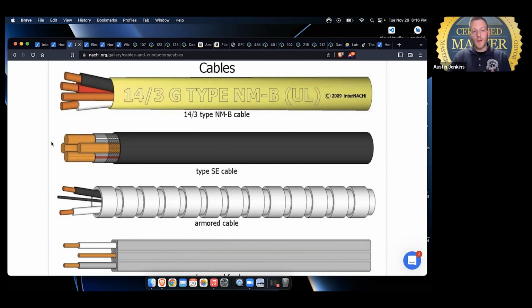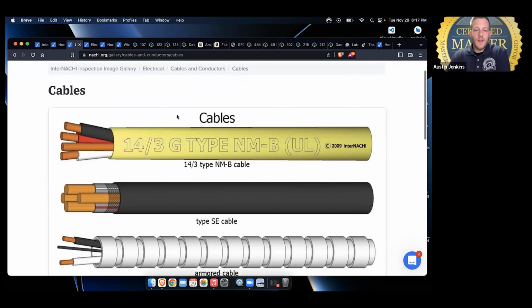Romex is a brand, not an actual cable type. This right here is a 14-3 non-metallic sheathed cable, one of the most common types of wiring you'll see in a residential structure. Usually it's 14-2, 12-2, 10-2, and so on. The first number is the gauge of the wire, and the second is the number of conductors. Earlier I said you have a black hot and a neutral, but this one's a little different: you've got the black hot, a red hot, and the neutral. Often 14-3 is used in 3-way switches and other lighting circuits, but that's just a general overview.